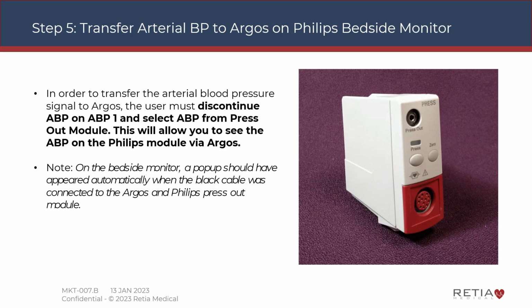Step 5. Transfer arterial blood pressure to Argos on Philips bedside monitor. This step will be required only if you are changing out the Philips ABP module. In order to transfer the arterial blood pressure signal to Argos, the user must discontinue ABP on ABP1 and select ABP from Press Out module. This will allow you to see the ABP on the Philips module via Argos. Note, on the bedside monitor, a pop-up should have appeared automatically when the black cable was connected to the Argos and Philips Press Out module.